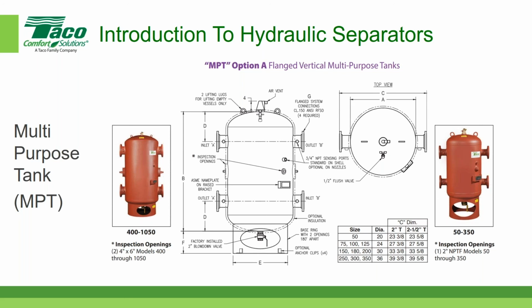Now, these multi-purpose tanks work extremely well in terms of hydraulic separation for hot water systems. There is a certain amount of mixing of the water that takes place, which ultimately translates into mixing of the temperature. But for chilled water systems, we would have to make sure that the internal components of the tank had baffles to ensure that we did not have mixing. So you don't want to have your primary water mixing with your secondary water unanticipated, so that you wind up with the wrong outlet temperature. So multi-purpose tanks can function as not only a hydraulic separator and an air and dirt separator, that's 2 devices, but also as a 3rd device, a buffer tank or buffer storage tank for both chilled water and hot water systems. And again, when it's a chilled water system, please come back to the factory so that we can talk about the problem of mixing to make sure that the tank is outfitted properly with baffling, so we don't have a mixing problem with chilled water.